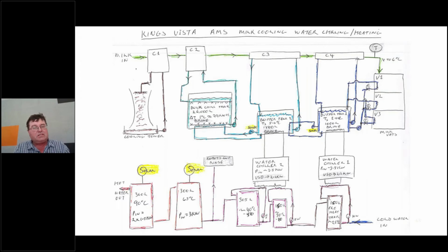We changed all the refrigeration circuits to chill water. So we reduced our total refrigeration gas from 40 kilos down to 6, as well as putting in these 2 small water chillers. Now, they're not water chillers that you buy off the shelf, because we didn't go that route. We went the route of putting coils within the buffer tanks. It eliminated freezing problems, eliminated some control circuits, extra pumps.